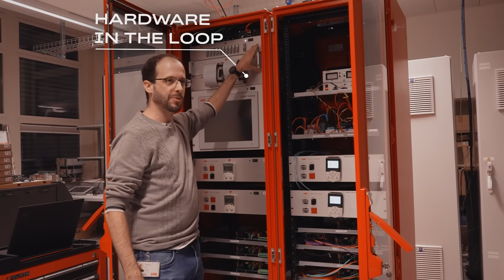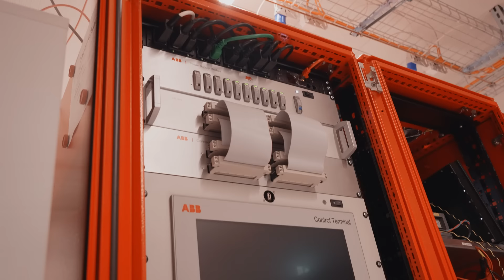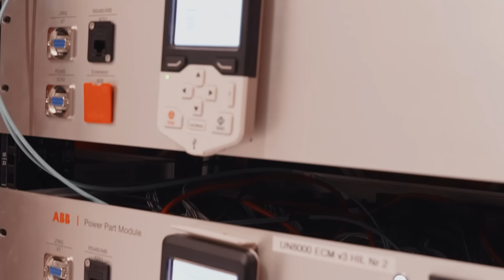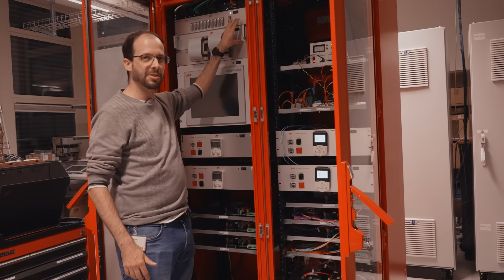In this test setup, the main components are our own controllers, of course, and also a so-called hardware-in-the-loop system. This system is capable of simulating a complete power plant with a generator, transformer, etc., and feeds the measurements to our controllers. It also emulates the converters of the excitation system, so that the controllers really give control signals to these emulated converters, and we can test this interface very thoroughly as well.